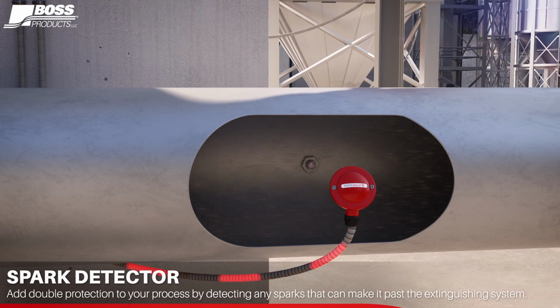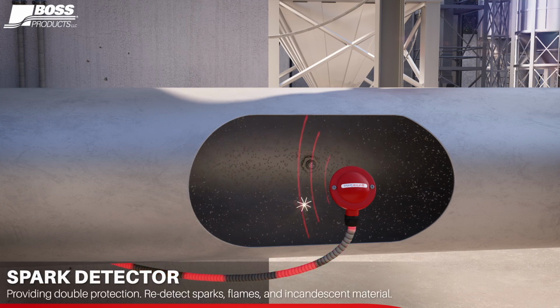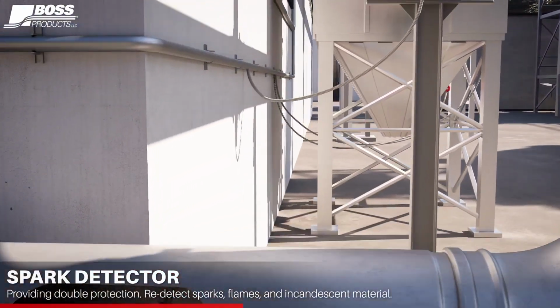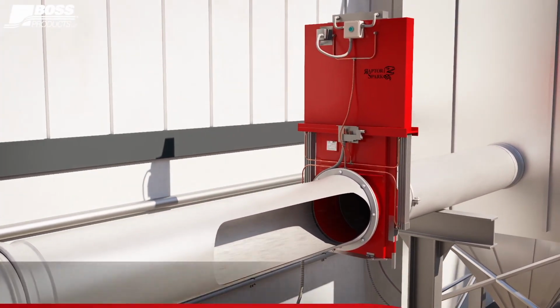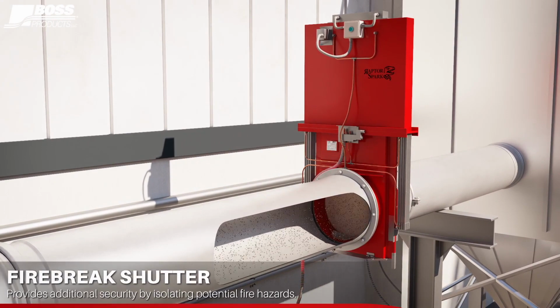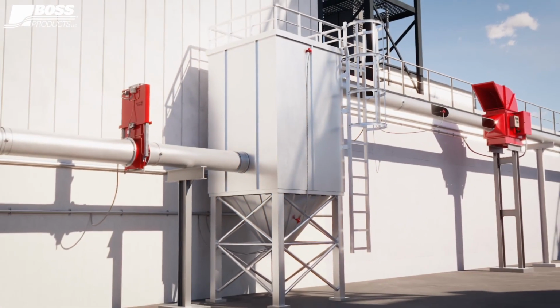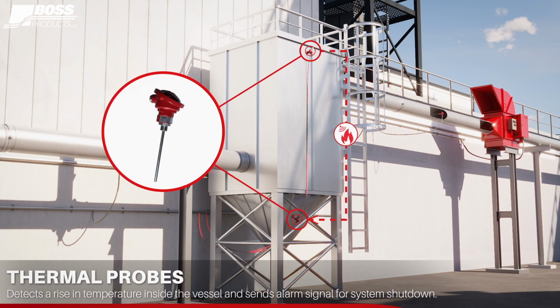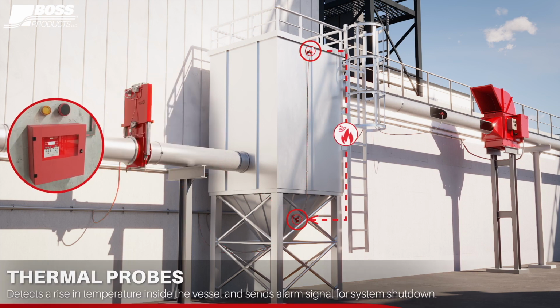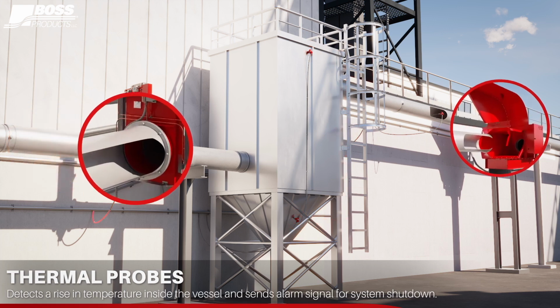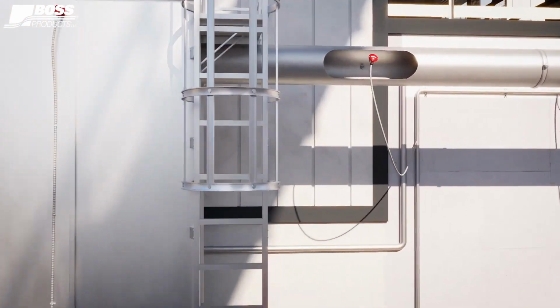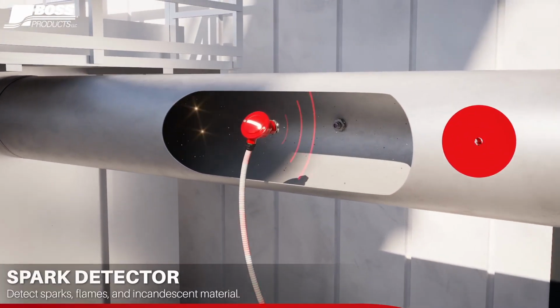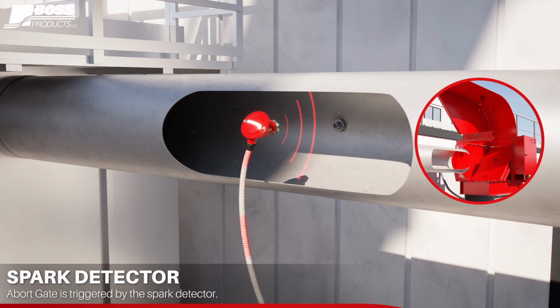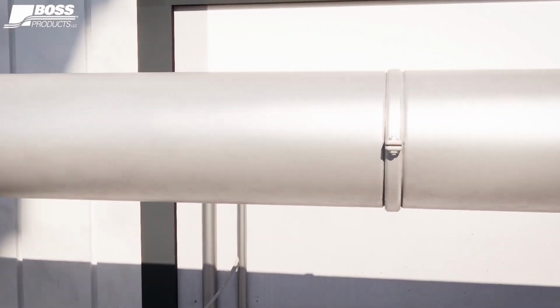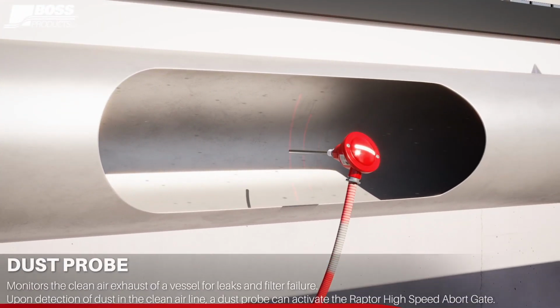We can also do redetect. I've done a lot of applications where sometimes they want to be safer than sorry, and we can do detect, extinguish, redetect, and then possibly put a mechanical fire break shutter as close to the vessel as possible. And basically what happens is it's a knife gate and it triggers and it shuts that duct down. Thermal probes is another additional layer of protection where basically they can either detect at a certain set point temperature or a rise in temperature that can also activate certain equipment as well. And broken bag detectors or dust probes on the clean air side, if you have maybe a bag that's broken or a leak in your filter.